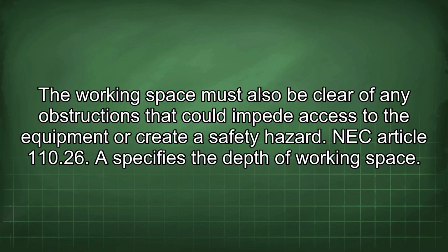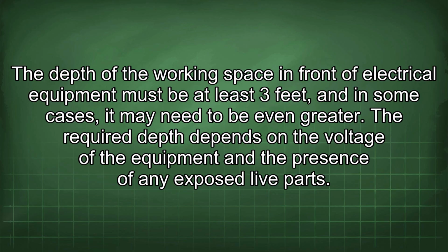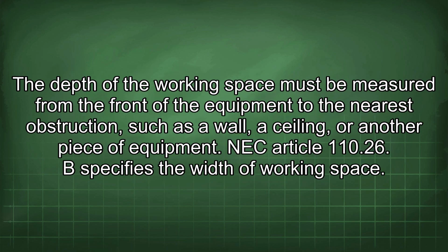The working space must also be clear of any obstructions that could impede access to the equipment or create a safety hazard. NEC Article 110.26 specifies the depth of working space. The depth of the working space in front of electrical equipment must be at least 3 feet, and in some cases, it may need to be even greater. The required depth depends on the voltage of the equipment and the presence of any exposed live parts. The depth of the working space must be measured from the front of the equipment to the nearest obstruction, such as a wall, a ceiling, or another piece of equipment.